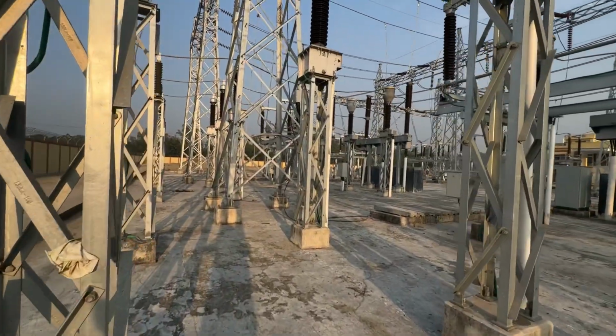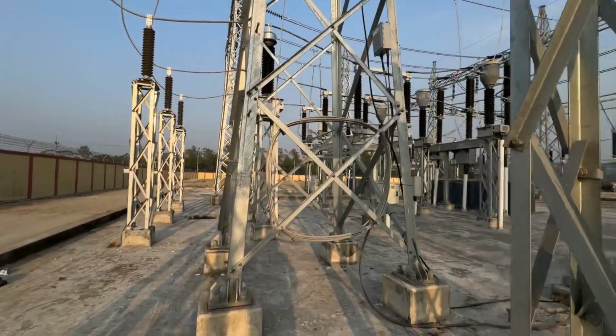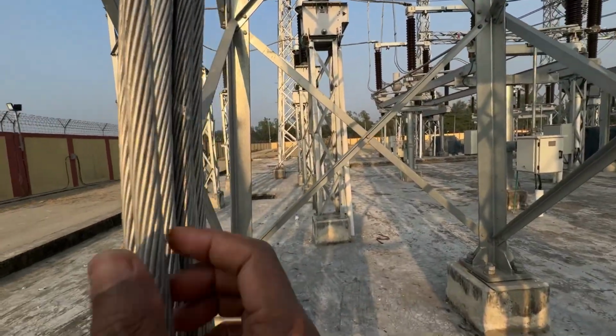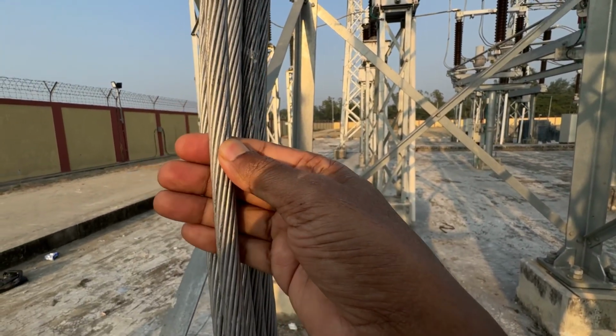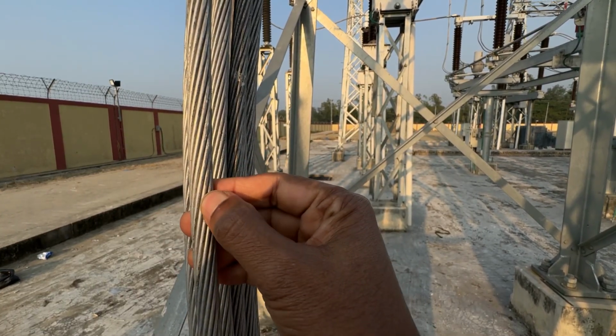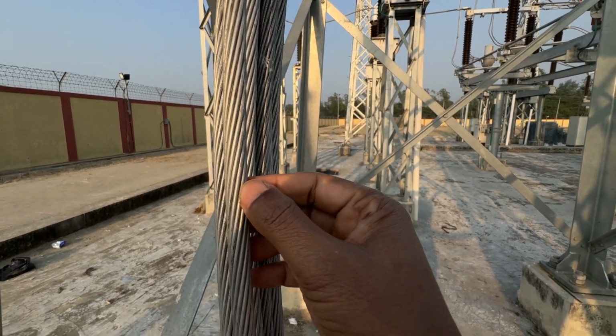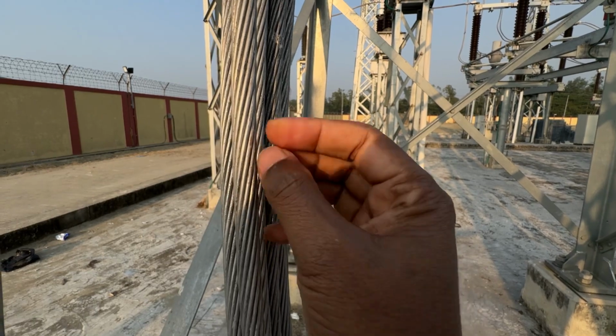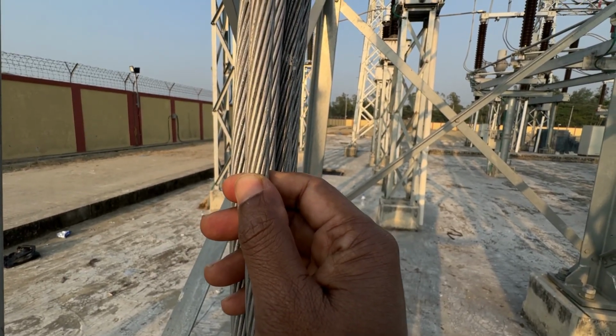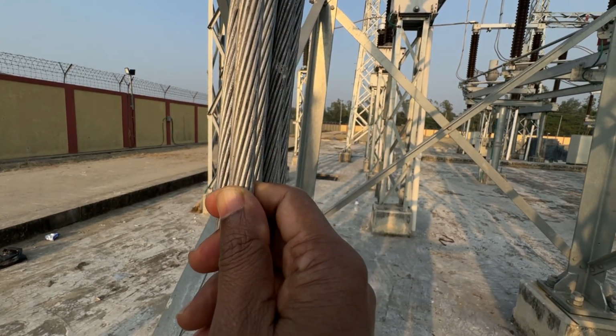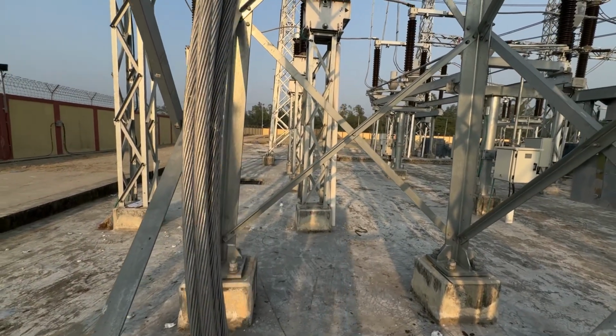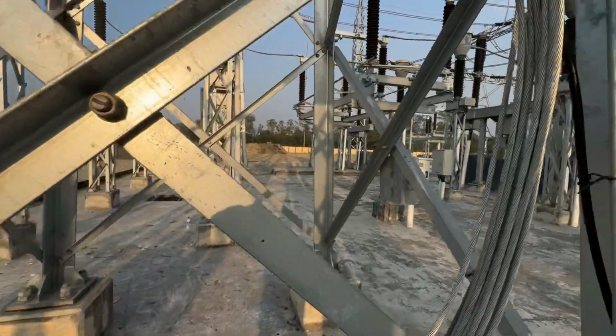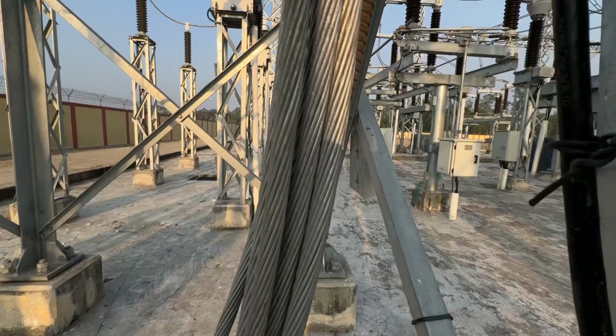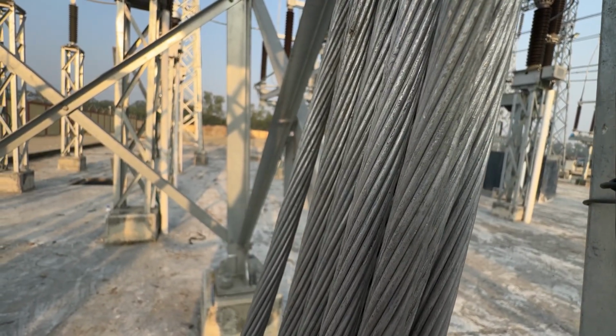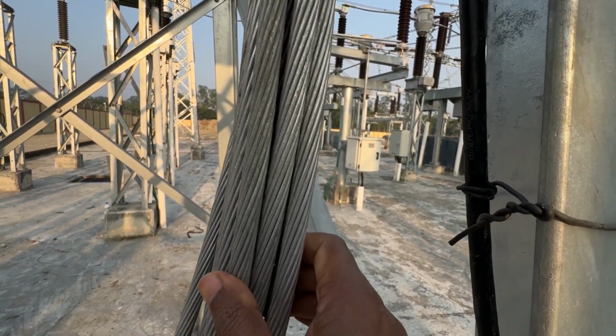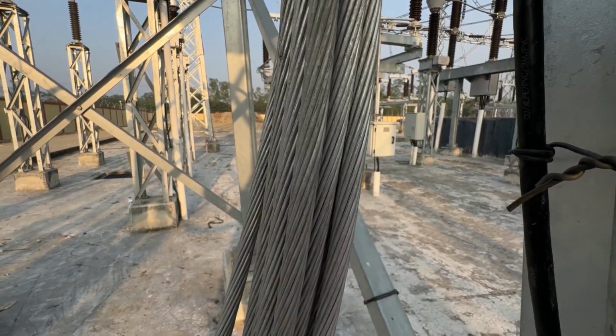Then how is the optical fiber inside an OPGW? Normally these are the OPGW conductor's strands. There is a hollow strand inside, and the optical fibers are inside this hollow strand. It may be 12 core, sometimes 24 core, sometimes 48 core optical fibers kept in this OPGW earth wire.